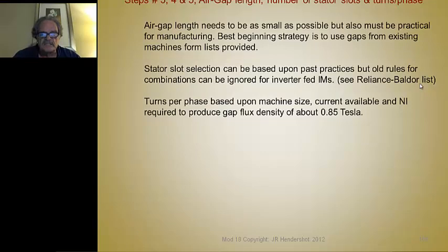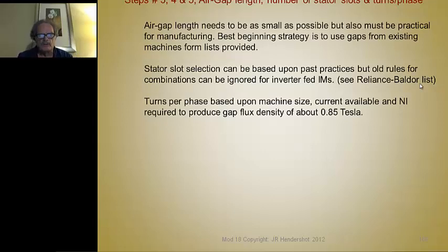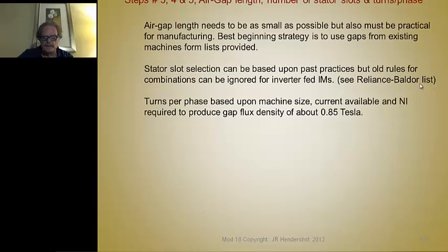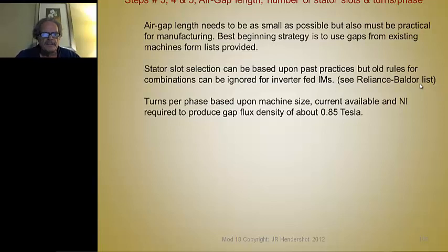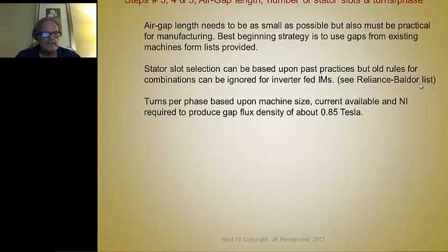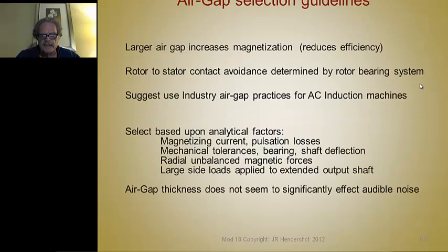Stator slot selection is fine to base on past practices, as long as you understand that some of the old rules for rotor combinations can be ignored because you're driving the motor with an inverter rather than fixed voltage and frequency from the grid. The turns per phase is based on machine size, the current available, and the NI required to produce the ampere-turns needed to achieve a gap flux density of about 0.85 Tesla in the air gap.